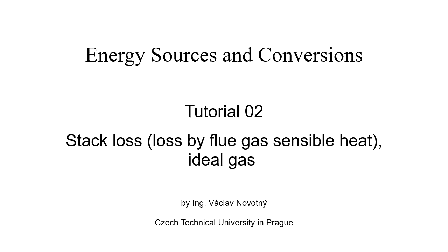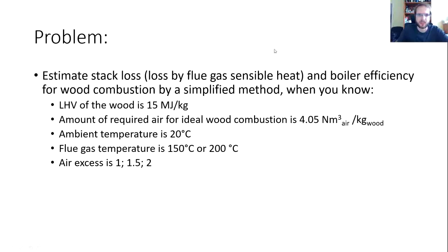In this short tutorial, we will have a look at the stack loss, a simplified way how to estimate boiler efficiency, and we will talk a little bit about ideal gas. Okay, so let's get to our problem. The problem goes that we have to estimate stack loss, or also we could call it loss by flue gas sensible heat, and boiler efficiency for wood combustion by a simplified method.